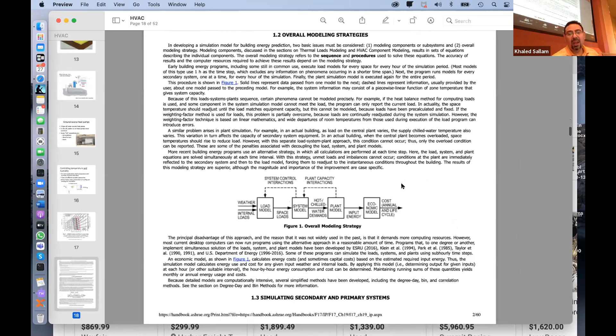This is from ASHRAE - here's basically how you design a new system. You have to figure out the load model: start with weather, internal loads like how many machines and computers, and figure out the load. Based on that load, you come up with the system model, so that house, plant, or classroom requires this many BTU per hour. Then you pick the architecture - a chiller, heat pumps, or a boiler. Based on this, you do the economic model and figure out how much it will cost over the lifespan of the project.